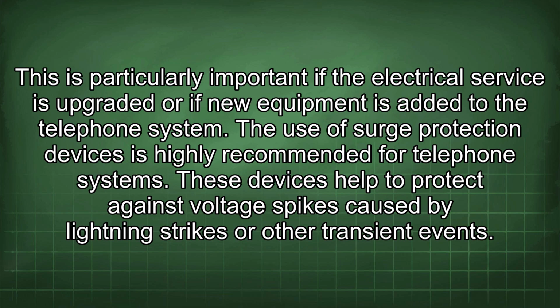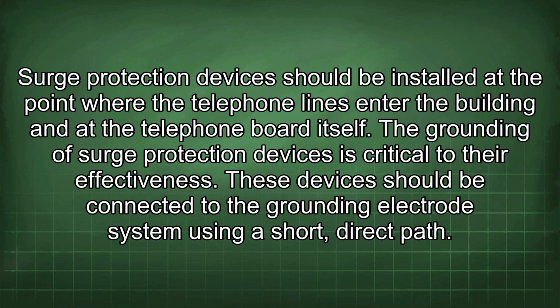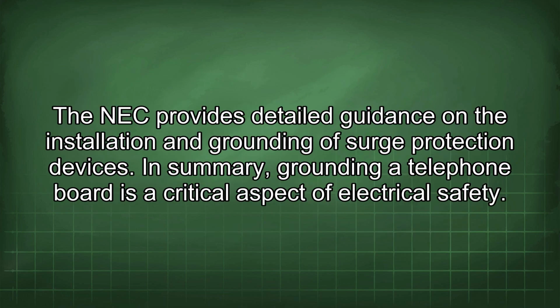These devices help to protect against voltage spikes caused by lightning strikes or other transient events. Surge protection devices should be installed at the point where the telephone lines enter the building and at the telephone board itself. The grounding of surge protection devices is critical to their effectiveness. These devices should be connected to the grounding electrode system using a short, direct path. The NEC provides detailed guidance on the installation and grounding of surge protection devices.